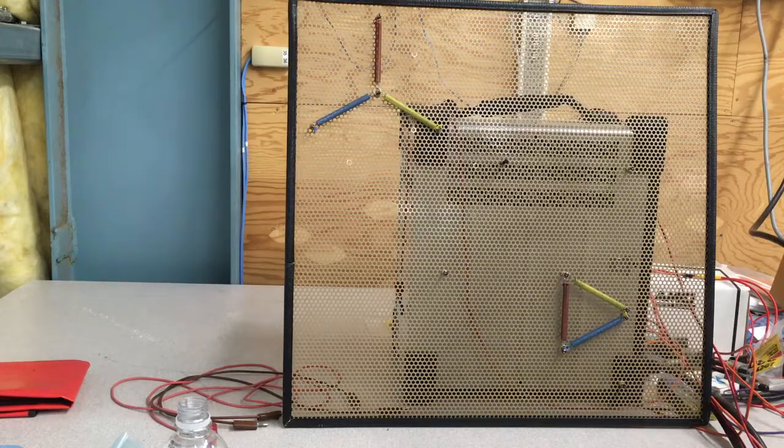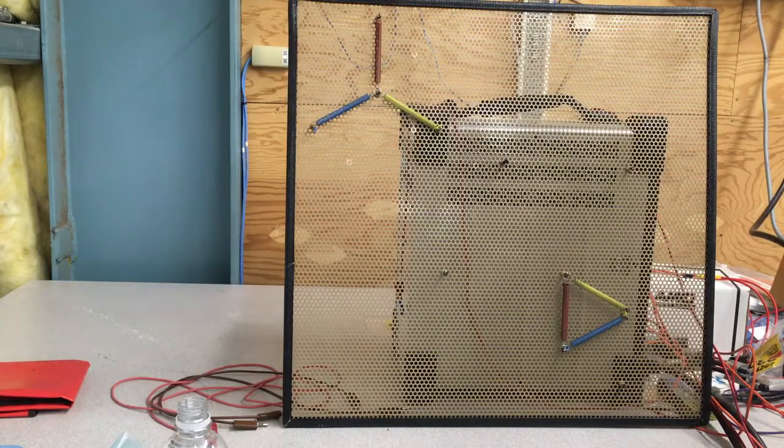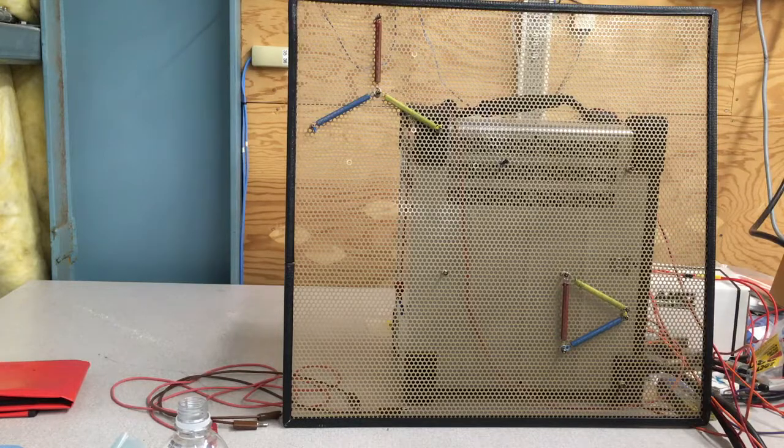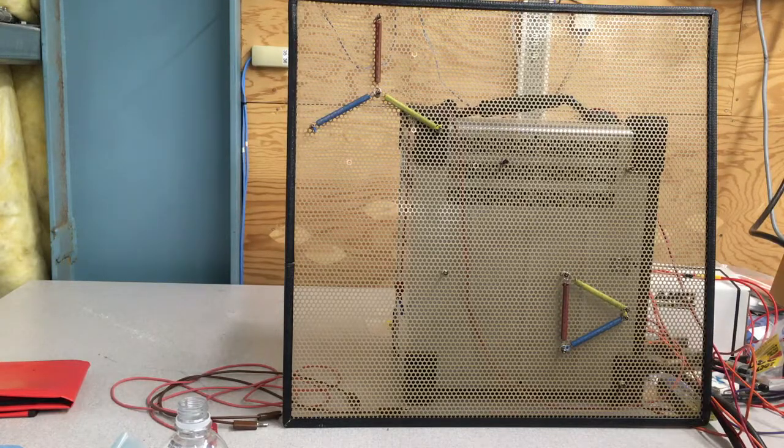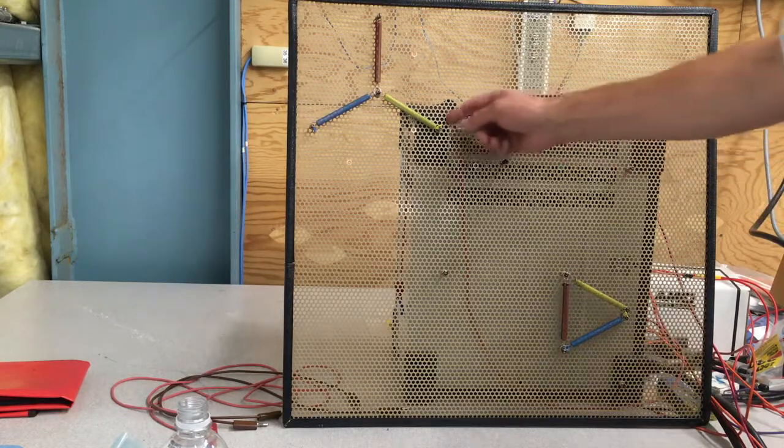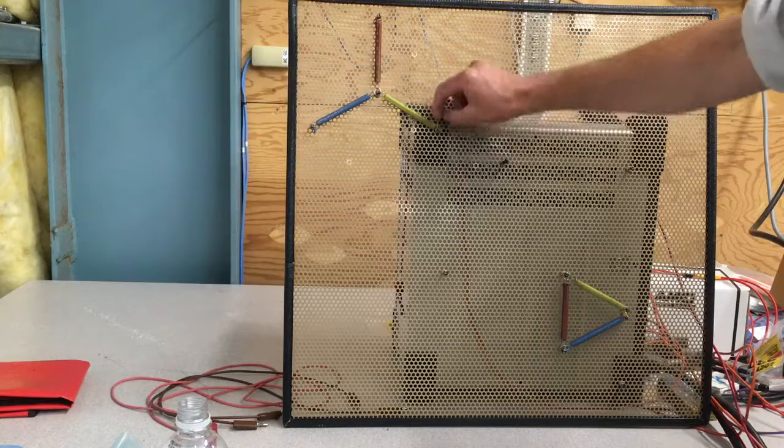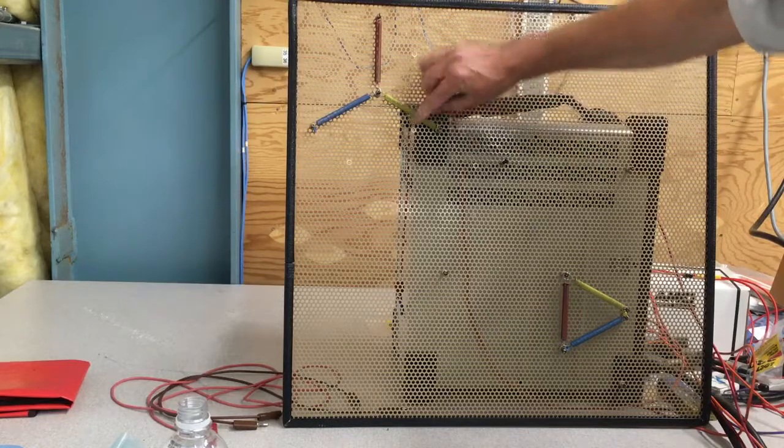This is to show what's going on with a set of wye broken delta PTs and how it works as a zero sequence filter. It might be kind of hard to see, but on these springs I have these little washers and that indicates polarity.